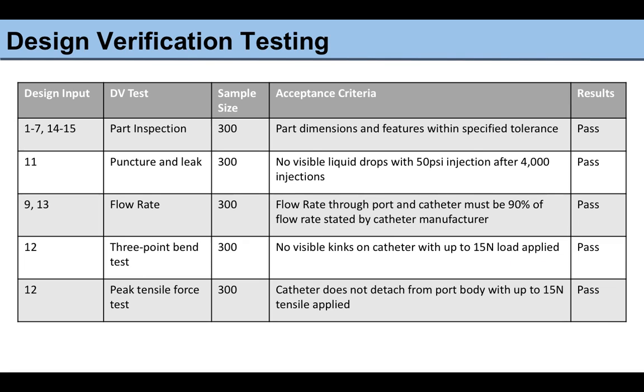One of the most critical components of producing a medical device is ensuring that it's safe and effective. To do this, you need to perform many tests on the device to show its safety and efficacy. When developing our tests for this product, we first developed test methods, then test protocols outlining the sample size and acceptance criteria needed to pass the test, and then we performed the tests and documented the testing results in reports.